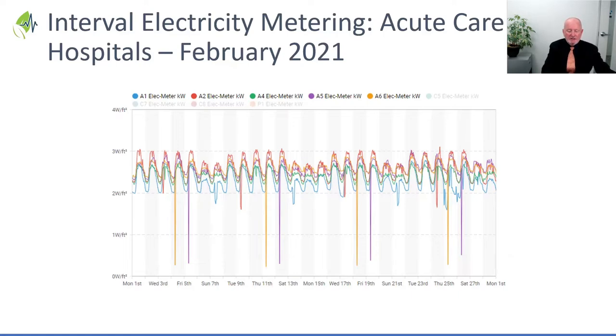And this scheduling, it sounds obvious, but it's not happening. Most hospitals with higher energy use are running too many systems 24/7. So the shape of your profile, by comparing it to top performing hospitals—and we'll show you the metrics in just a moment—tells you both: did you get the peak right? Which means, did you design your lighting well? Did you design your fans well? Are your pumps about right? But the valleys are even more instructive. Are you operating the facility well? Are you doing a good job with scheduling?